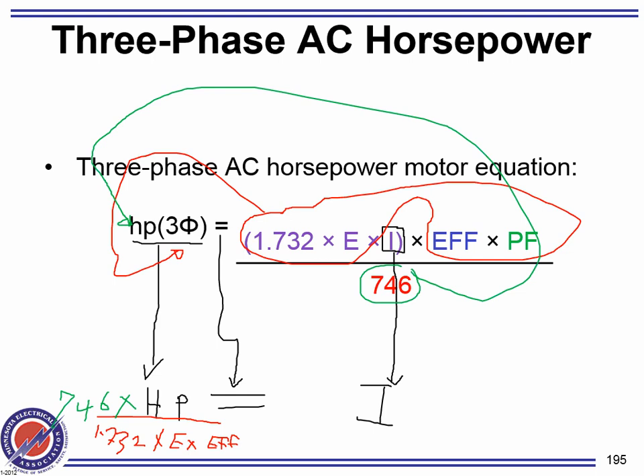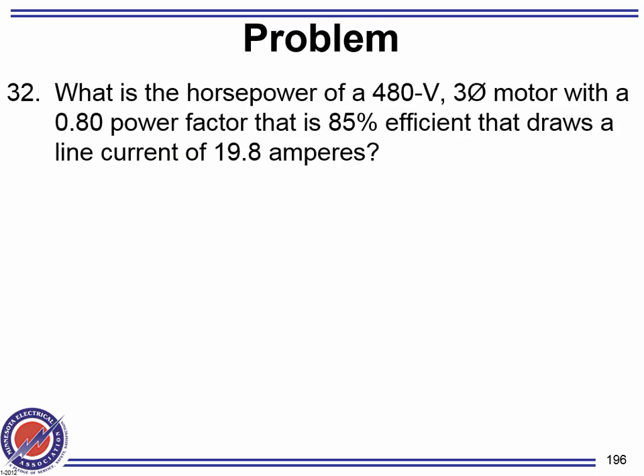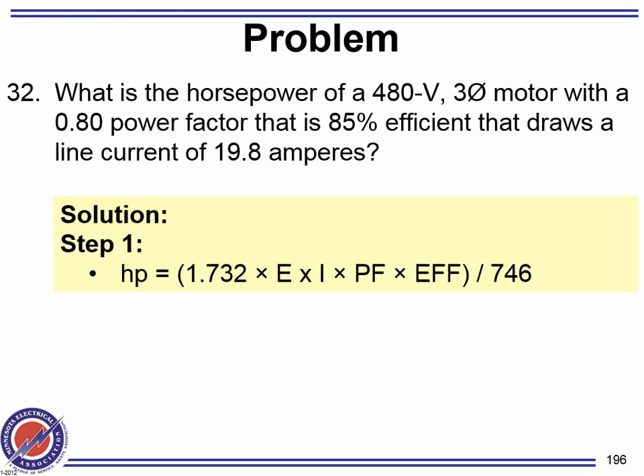Okay, now we flip the formula. Don't let it bother you guys. What is the horsepower of a 480 three-phase motor with this power factor? Everything is given. You have the voltage, the efficiency, the power factor, and the amps, and they're asking you to find the horsepower. Is it three phase or single phase? Three phase. So don't forget the 1.732.